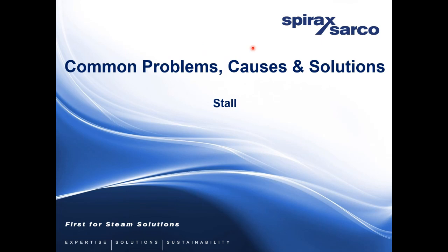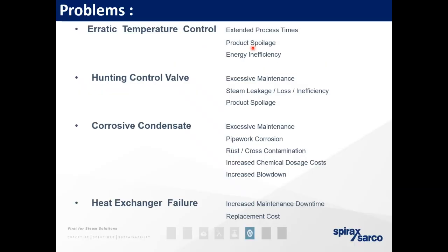So, common problems, causes and solutions for stall. Many of you have seen stall in your heat exchangers, for instance. So the problems, what it causes: erratic temperature control, extended process times, as we said, product spoilage, so you're having to dump product, and energy inefficiency, so again that's referring to longer heat up times. Hunting of control valves, where you see a control valve moving up and down more than you would expect it to, we call that hunting. That will lead to excessive maintenance, steam leakage and loss inefficiencies, and product spoilage again. If you can't maintain the temperature because the control valve is hunting, it's going to spoil product because you can't guarantee the temperature of use.